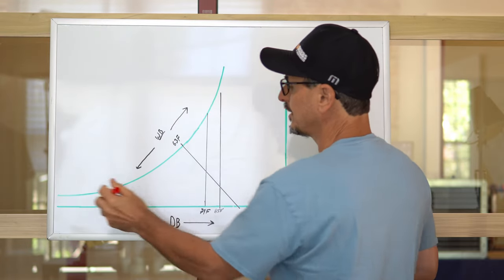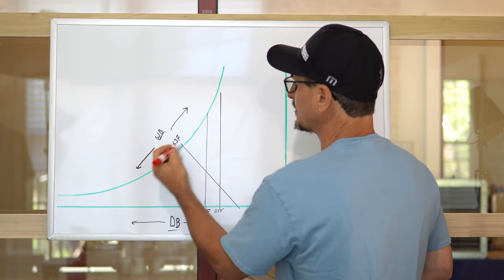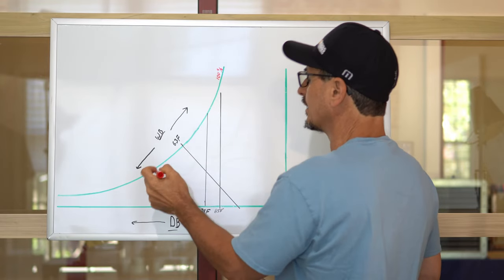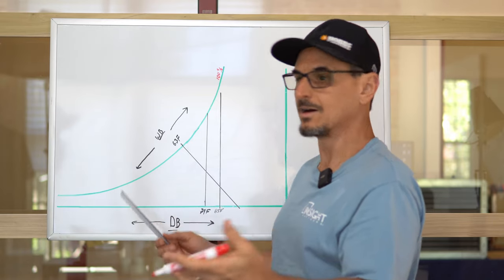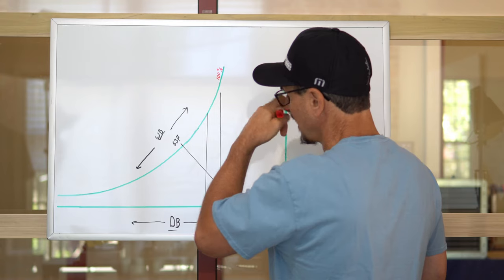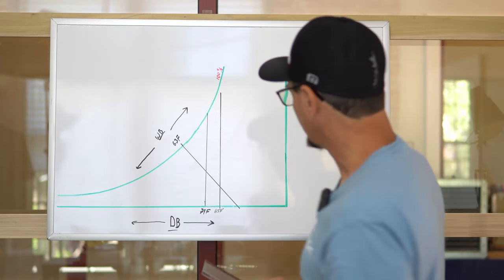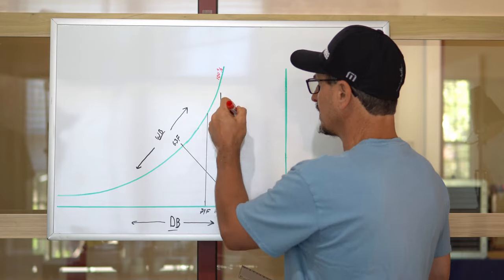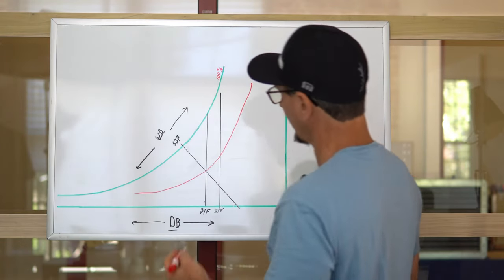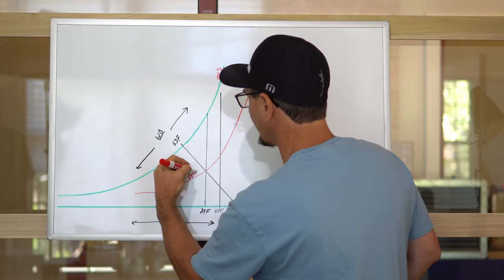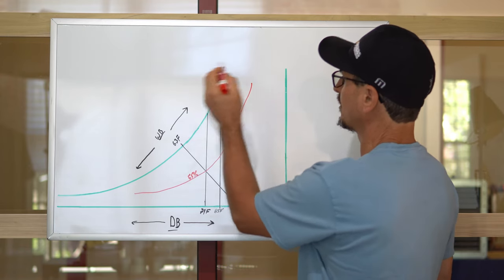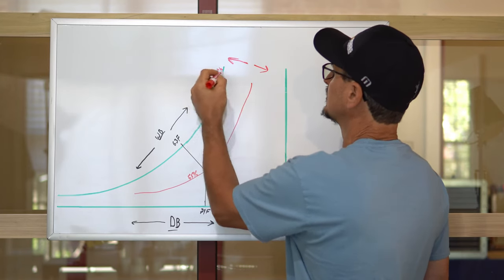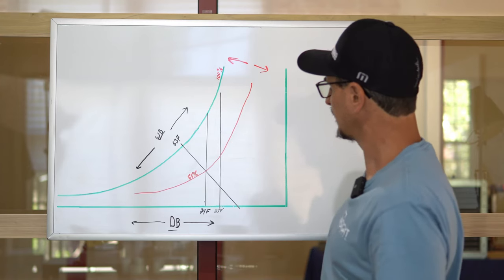The relative humidity lines follow this outer curve. This is 100% RH — fully saturated; the air cannot hold any more water. What happens after that? You get rain, you get fog. The relative humidity lines run curves like this, and the office is at 55% RH. As you go toward the saturation curve, you're increasing humidity; going the other way, you're decreasing humidity. If you were to draw vertical dry bulb lines at 86, 87, 88, 89, add the diagonal wet bulb lines, and then these curves — that's how the chart is built.